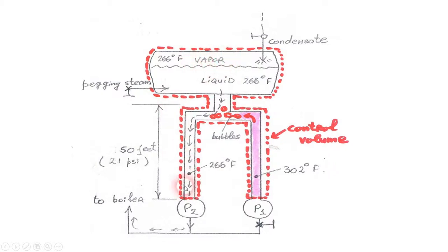But the standing head of 50 feet is fundamentally what the NPSH is for both pumps. However, at the reduced pressure and reduced temperature, the temperature in leg number 2 keeps on reducing. That's what saves the pump, and it keeps on running. The temperature at the pump number 1 leg, 100 feet of that, or 50 feet in this example, remains hot. The pressure is dropping. Therefore, it's no longer 50 feet of cold fluid, but 50 feet of the hotter fluid.